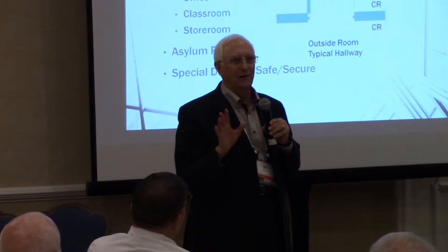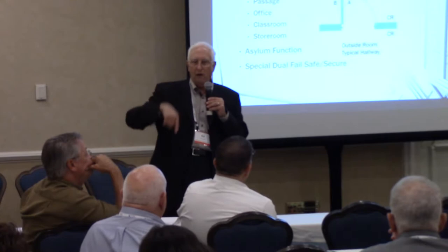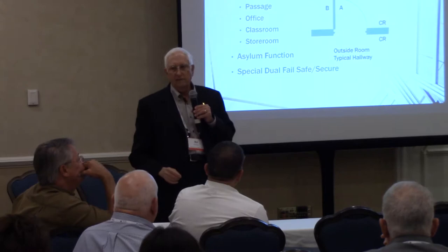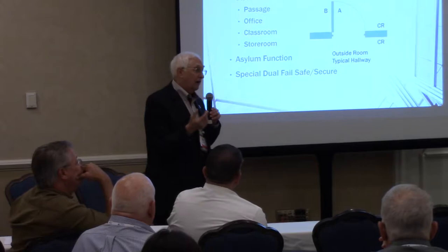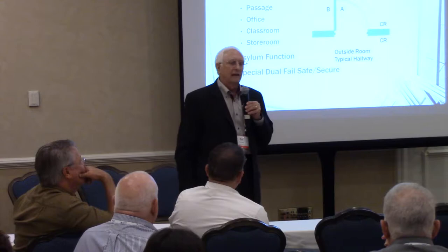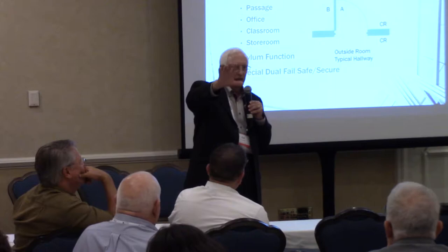I did a job in Oregon with a lot of traffic. We used panic hardware and fixed it so it was electrically dogged open all the time, dropping back to latched on fire alarm activation. We lost power and it would latch, giving us our fire rating. We also had mag locks on those doors, so during a fire the mag locks lost power and the panic hardware started working — we met the fire code criteria.